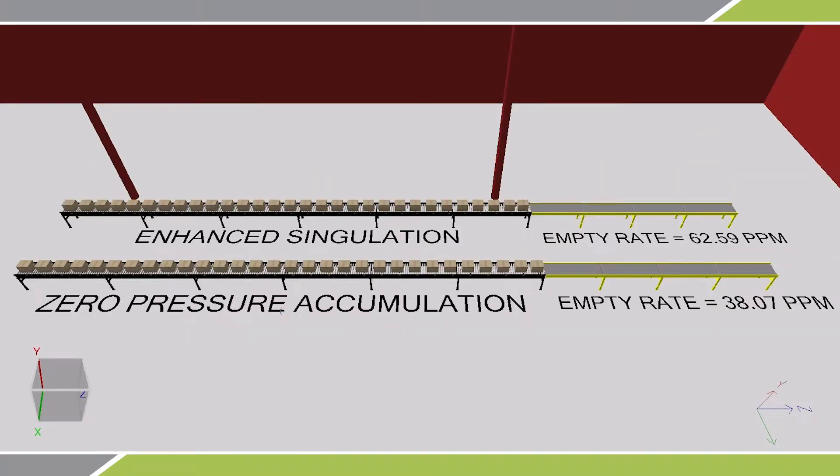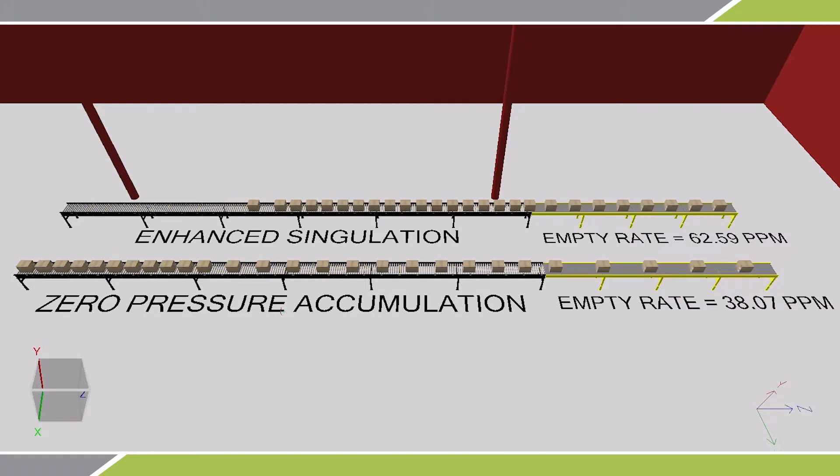When the conveyor lines are released, enhanced singulation or slug release energizes all zones simultaneously, whereas ZPA waits for the downstream zone photo eye to be clear of product before energizing.